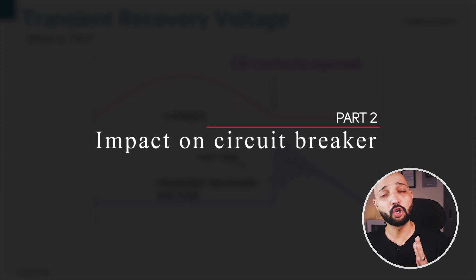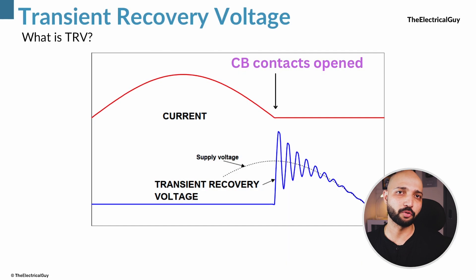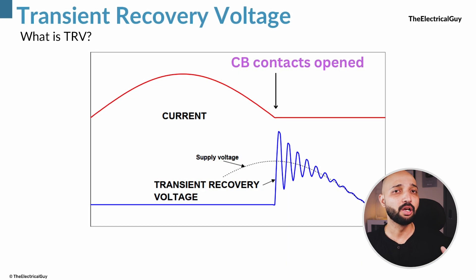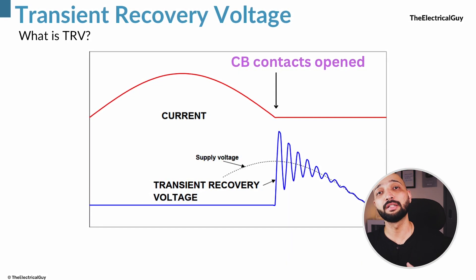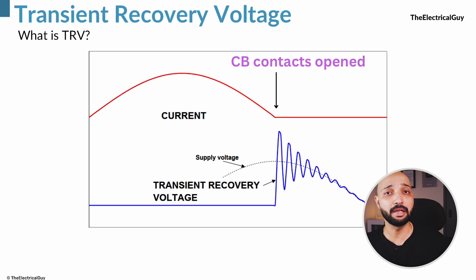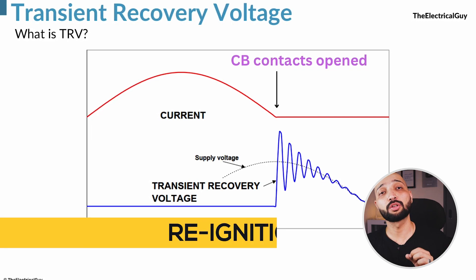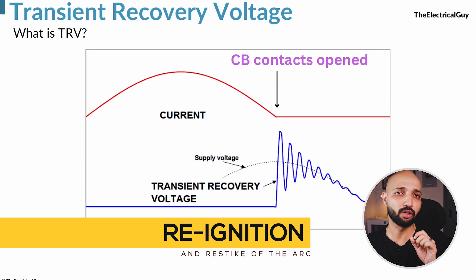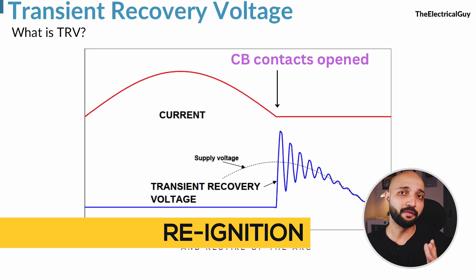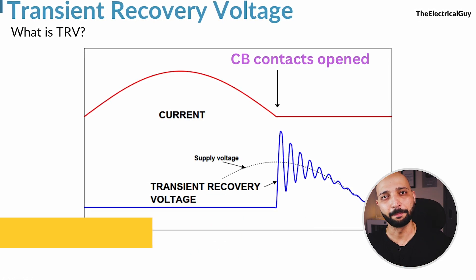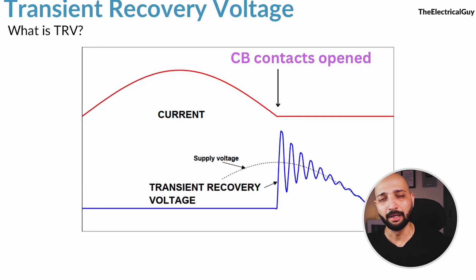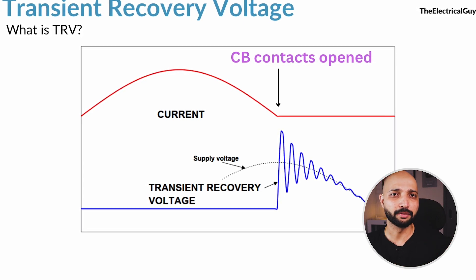As we have seen, transient recovery voltage appears across the contacts of the circuit breaker after fault interruption for a very short duration of time, and its value is very high compared to the normal system voltage. TRV can cause re-ignition and re-strike of the arc if the breaker fails to handle it, which will keep the fault running and can damage the system.